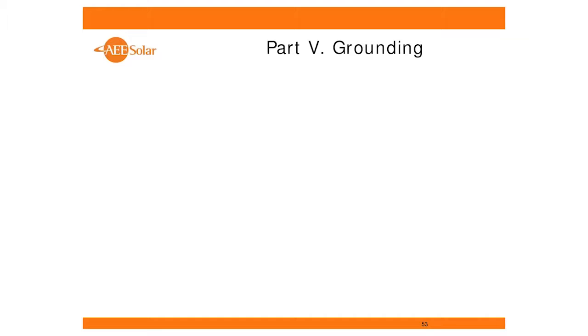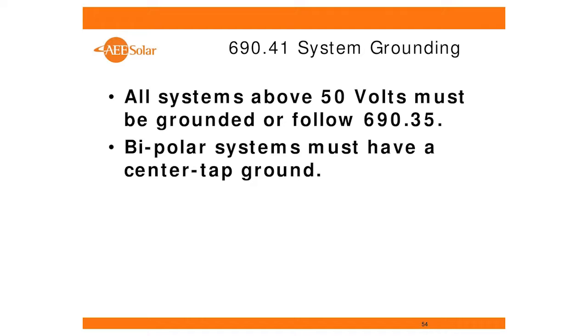Okay, let's see. We want to talk about grounding. So grounding happens after all this stuff. Part 5 in the code talks about grounding. And there are 2 types of grounding we have to be concerned about. The first is system grounding, which is referencing the current carrying conductors to earth. And then we have equipment grounding, which also entails bonding. We've actually changed the terminology to bonding and grounding for equipment grounding just to make it clear, whereas for systems, we're talking about grounding the system.